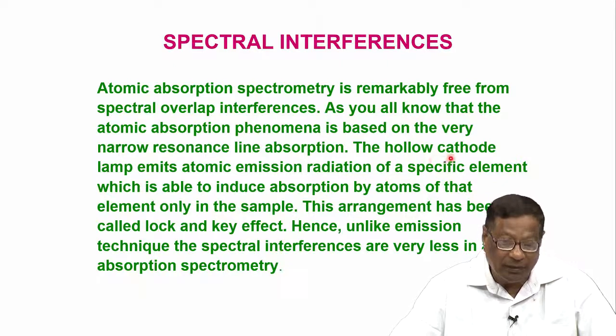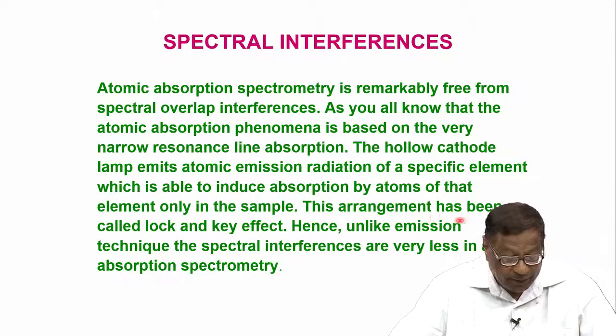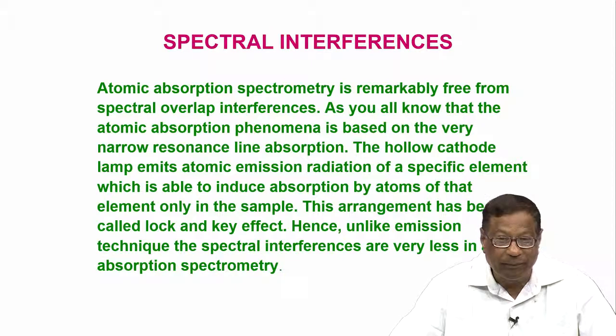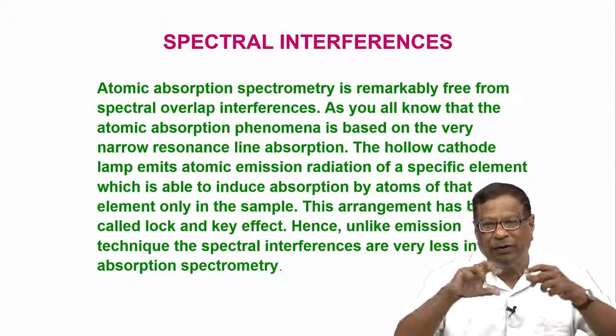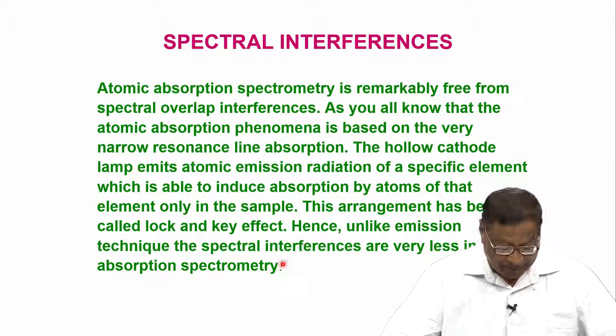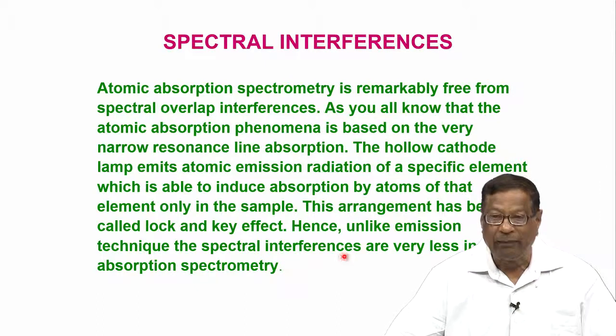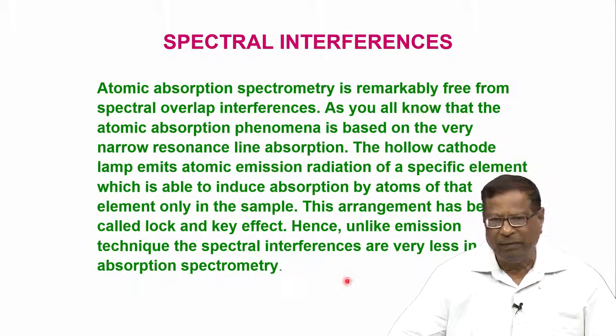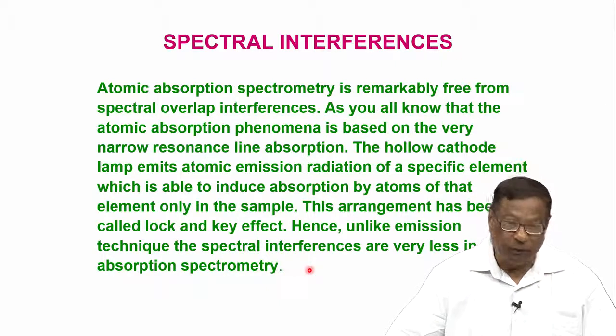The hollow cathode lamp emits atomic emission radiation of a specific element that is able to induce absorption of atoms. This arrangement is called the lock and key effect — the hollow cathode lamp emits the radiation and the free atom absorbs it. Unlike emission techniques, spectral interferences are very few in atomic absorption spectrometry because emission lines may be several hundreds, but resonance lines are very few — one or two, not more.